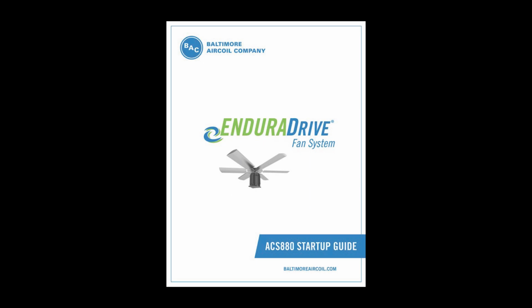Step 2. Setup. This section will cover how to correctly set up your Enduradrive Fan System VFD. The ACS880 VFD firmware walks you through basic questions for setting up the cooling tower. The review provided here corresponds to steps 4 and 5 of the Enduradrive ACS880 Startup Guide.